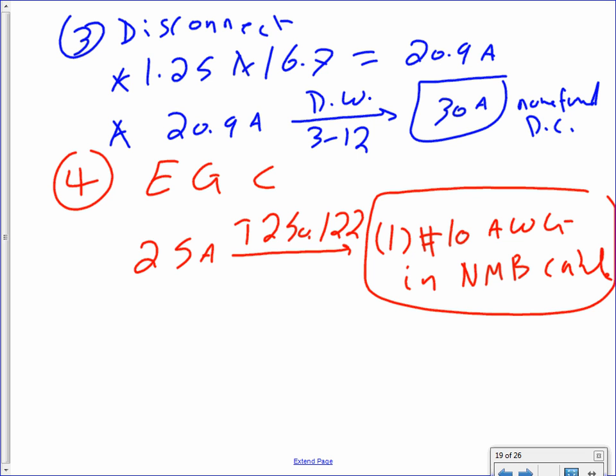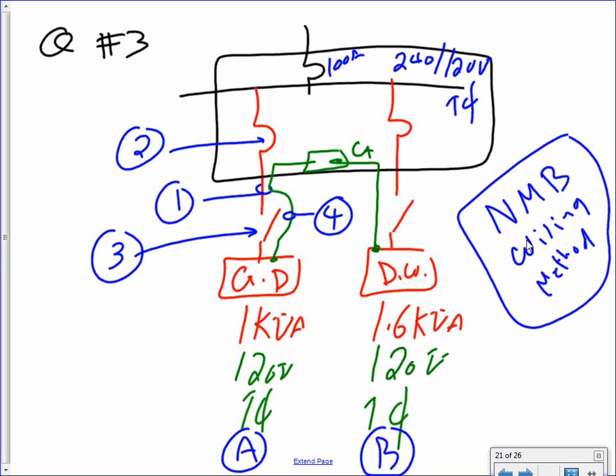Any comments, guys? Any questions about that? Okay, the last one, and I promise this is the last one, is this. We have a garbage disposal and a dishwasher, and we're going to do the same thing for one garbage disposal, one dishwasher, shall we? So if you guys take a few seconds to sketch, this is the last example that we have. We have a garbage disposal and a dishwasher, 1 kVA, 120, and 1.6 kVA, 120 single phase. We need to size the disconnect, the overcurrent protection device, and so forth.